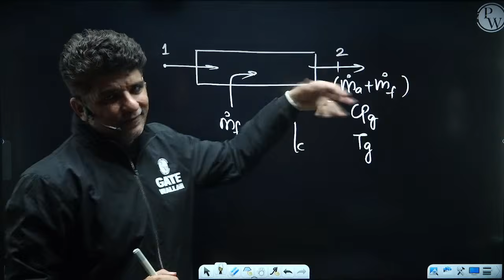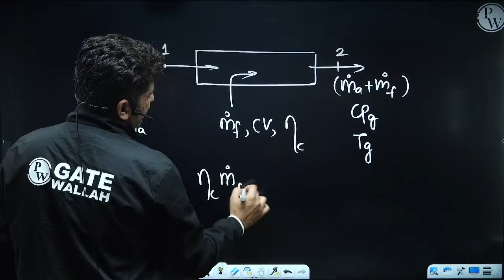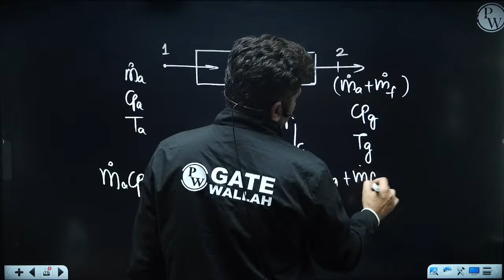So in generalized equation, we know that the enthalpy coming in is m dot A Cp air into T air, plus the energy which is getting added, m dot F into calorific value. That will be equal to mass flow rate of air plus mass flow rate of fuel multiplied by Cp gas into T gas. Okay.